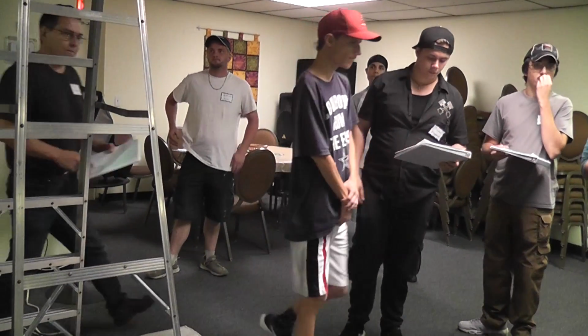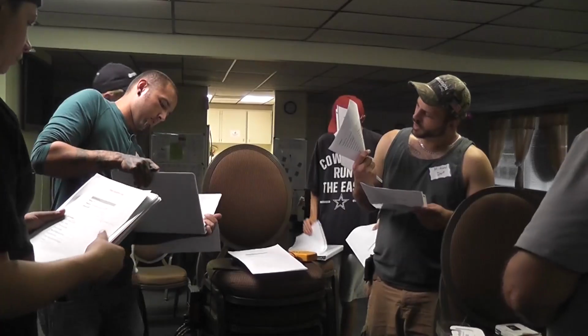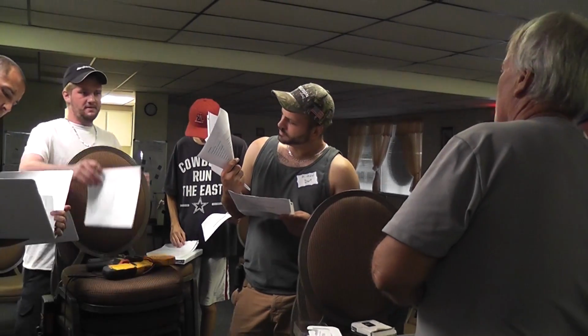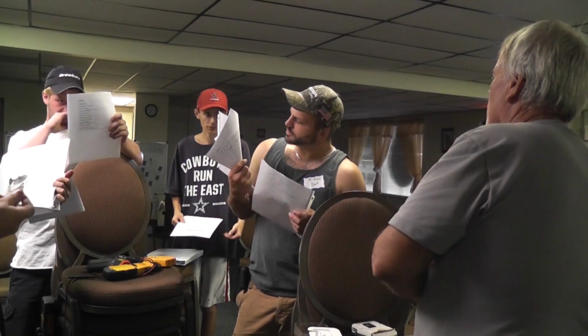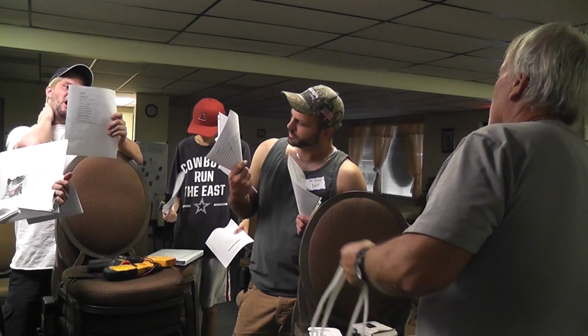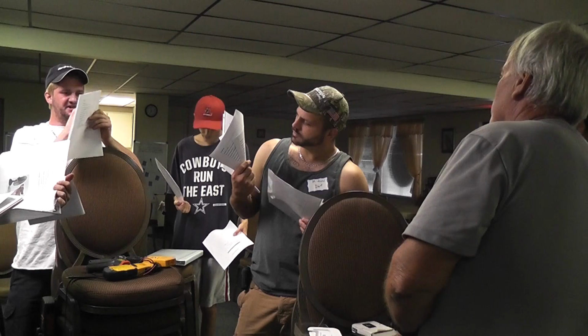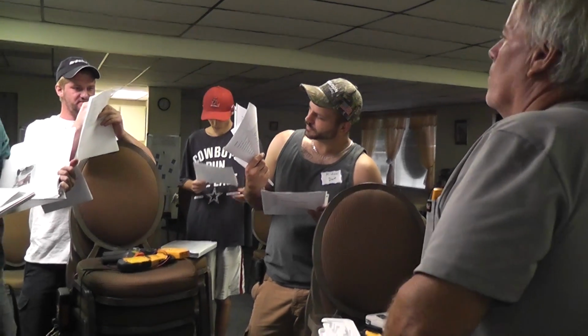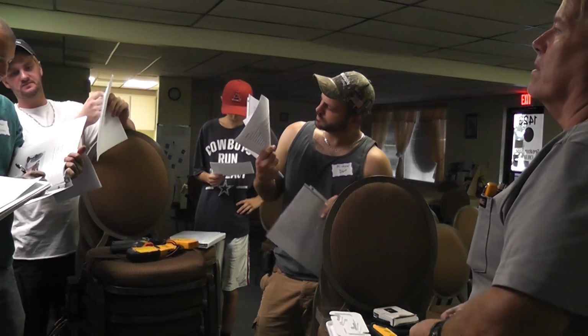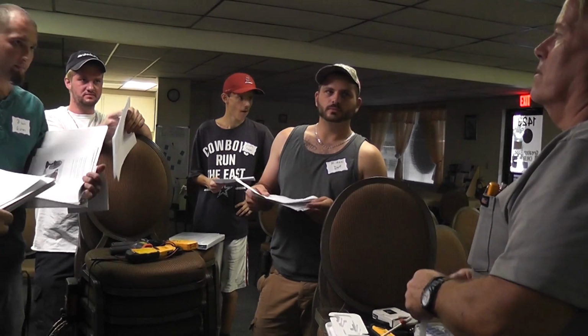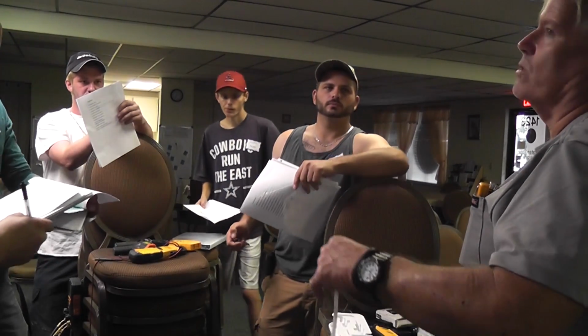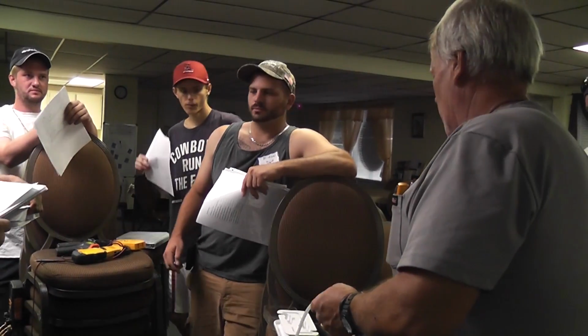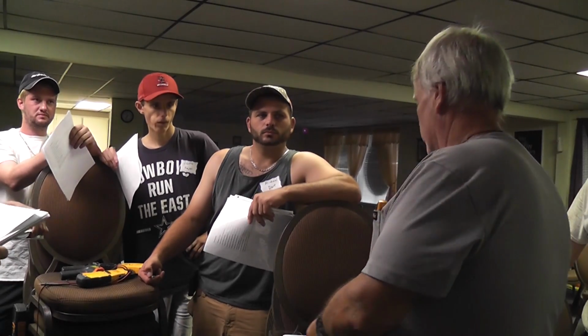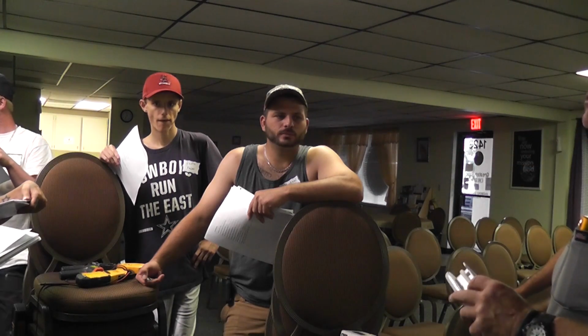Somewhere should be the notes on what the standard supply static pressure is and the return pressure. Supply is 0.05. Supply static pressure would be 0.01. 0.05 return. So 0.1 is the supply. We don't have enough pressure in that duct. Ductwork's the wrong size. At one point, I would guess this was a 5-ton system and somebody downsized it. We can't get the pressure out of the ducts.